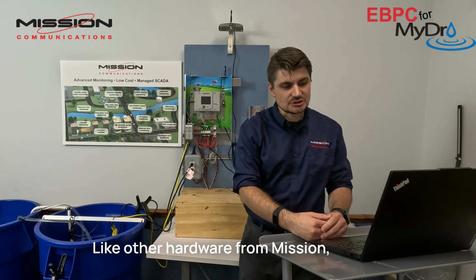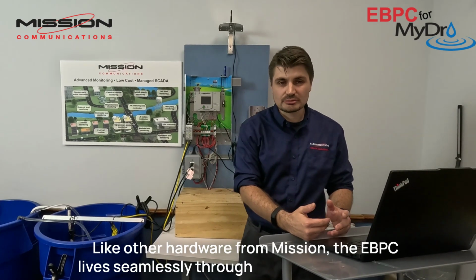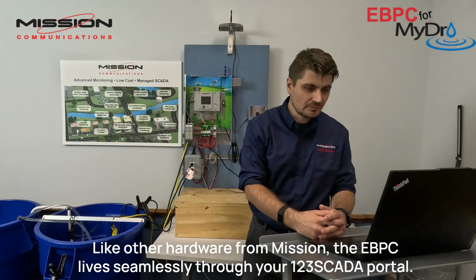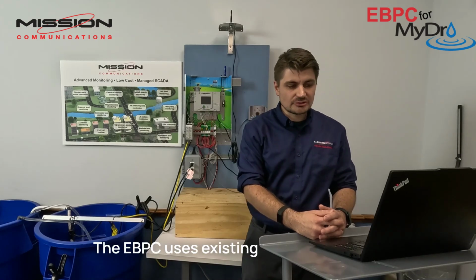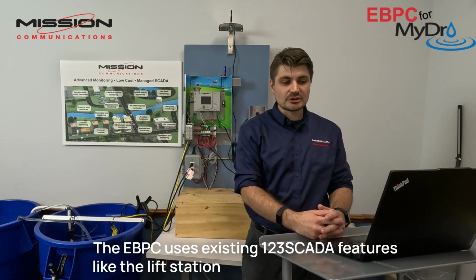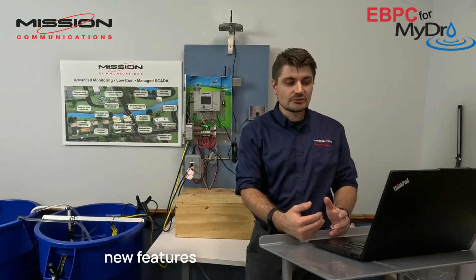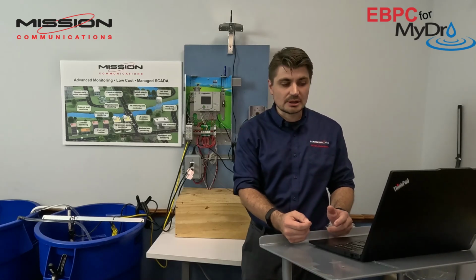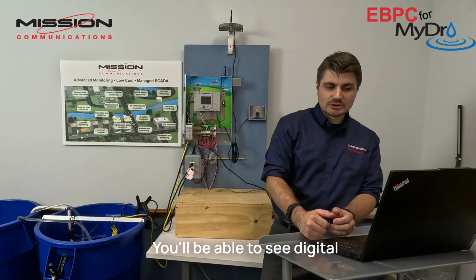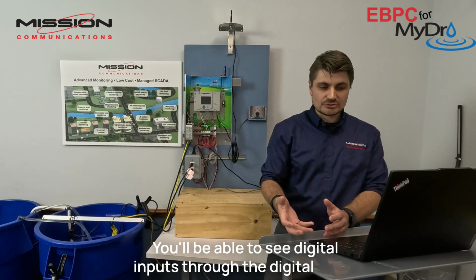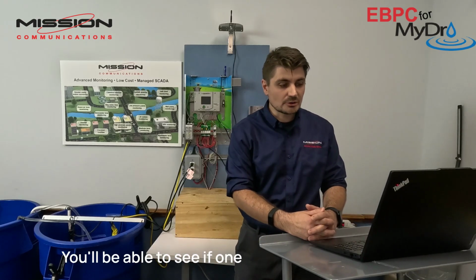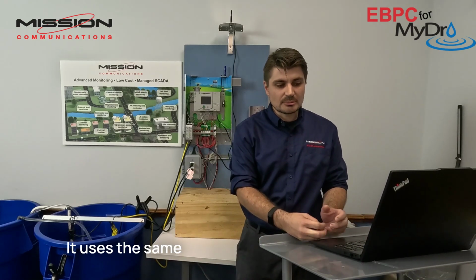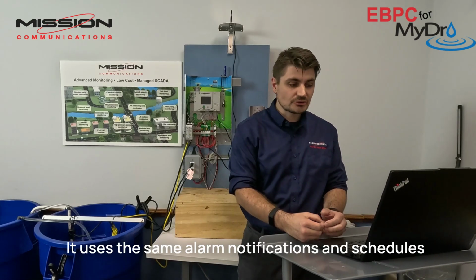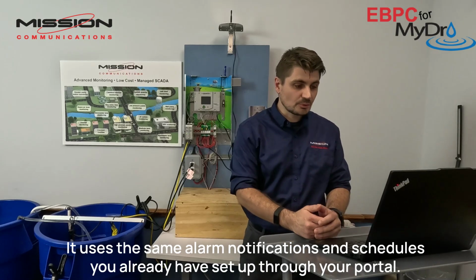Like other hardware from Mission, the EBPC lives seamlessly through your 123 SCADA portal. The EBPC uses existing 123 SCADA features like the lift station widget, while introducing new features like the remote force run command. You'll be able to see digital inputs through the digital table. You'll be able to see if 1 or 2 pumps are running. It uses the same alarm notifications and schedules you already have set up through your portal.